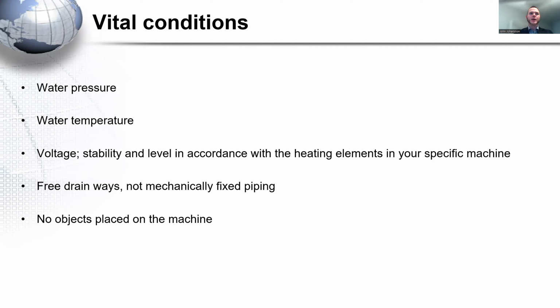Free drainways and not mechanically fixed piping. What do we mean with that? By free drainways, we mean that you should have a drain pipe which is not smaller than 50 millimeters in diameter. And this is to make sure that the machine can drain all the water necessary within the time stipulated by the controller in the machine.